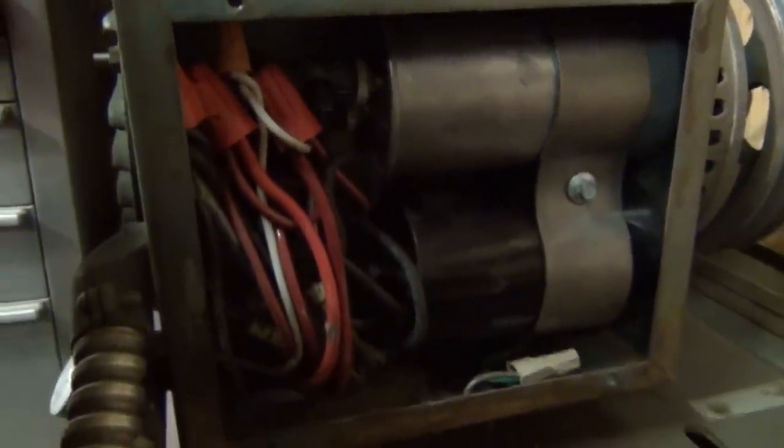So these are our two capacitors that are in here. You can see they are fairly decent size. This one up here is most likely our run capacitor and this one is most likely our start capacitor right here. And this is what I suspect is bad. So we'll go ahead and take it out of there and do some testing.